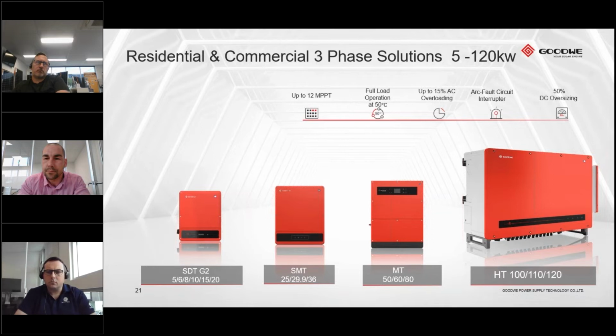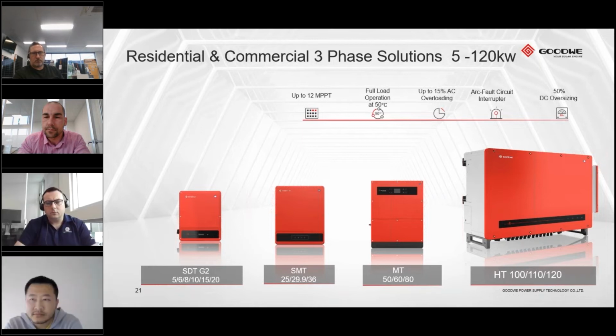We think we've really got all the features that we wanted in this product. It's got 15% AC overloading, and I'll talk more about that in a minute. What we mean by that is, let's say, for example, you've got a 100 kilowatt inverter and you've put 110 or 120 kilowatts of panels, or sorry, at least 15% more panels, it's actually going to produce 15% more. So it will actually produce more than 100 kilowatts if you oversize it with panels. And that's certainly a really big selling point. And the regulatory authorities will always go by the nominal output of the inverter. Therefore, we're able to produce more.